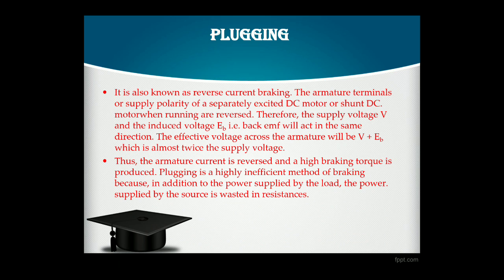The armature current is reversed and a high braking torque is produced. Plugging is a highly inefficient method of braking because, in addition to the power supplied by the load, the power supplied by the source is also wasted in resistance. If the braking torque is highly increased, current also increases, generating more heat. It is an inefficient method for DC motors, but it is a very efficient method in the case of three-phase induction motors.